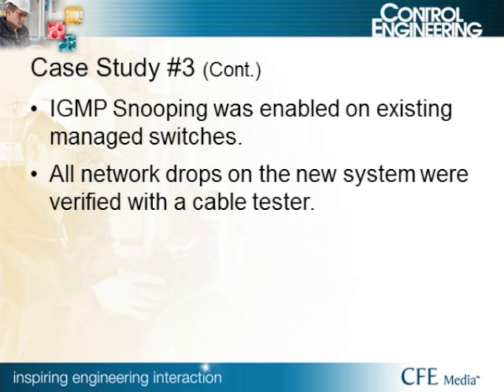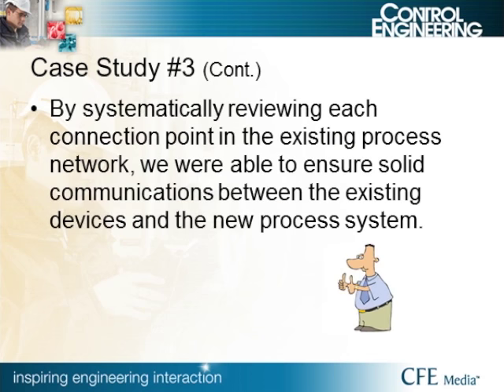We enabled IGMP snooping to contain broadcast storms. All connectors were re-checked and reinstalled, verified with a cable verifier, and we provided a verification printout of all connectors checked. All new network drops in the new system were verified with our cable tester as well. By systematically reviewing each connection point, we ensured a solid communications path between the existing system and the new process system, giving us confidence that when controlling field devices everything would work as intended.